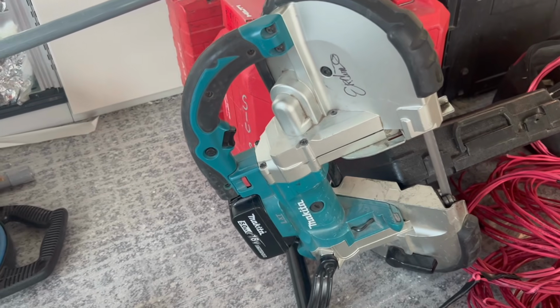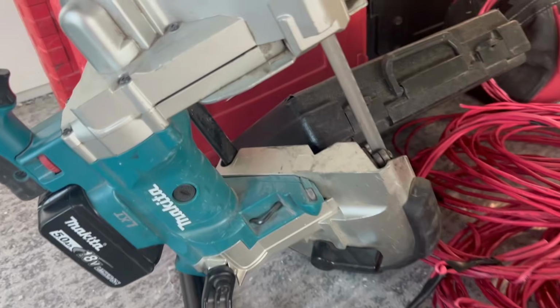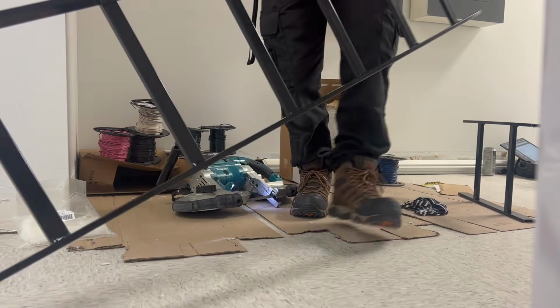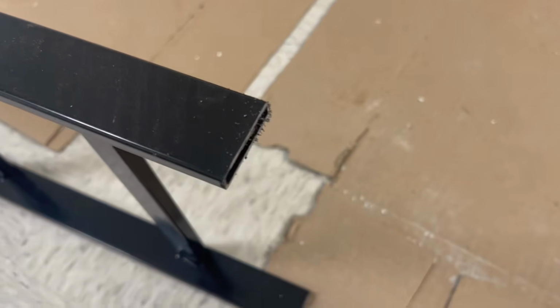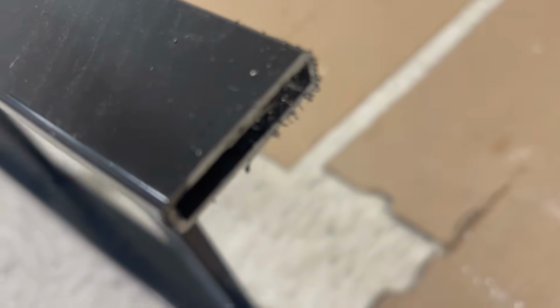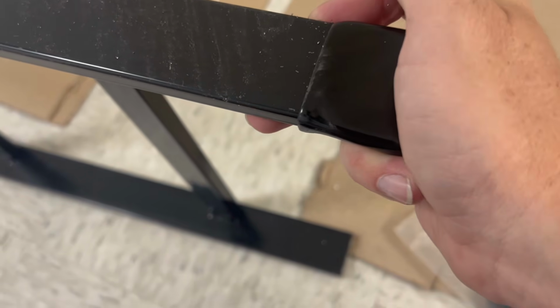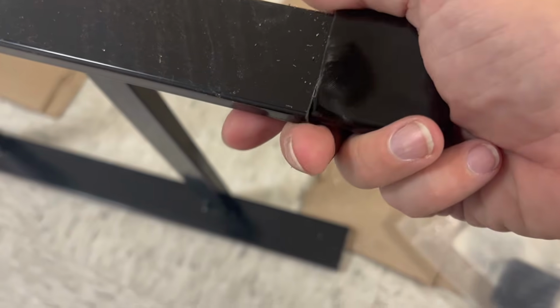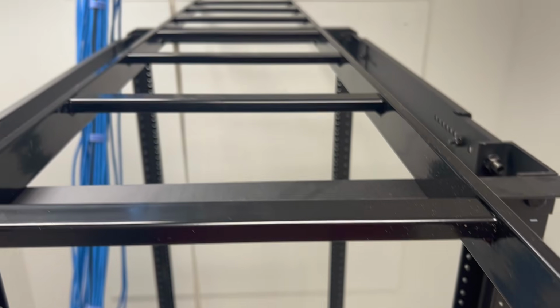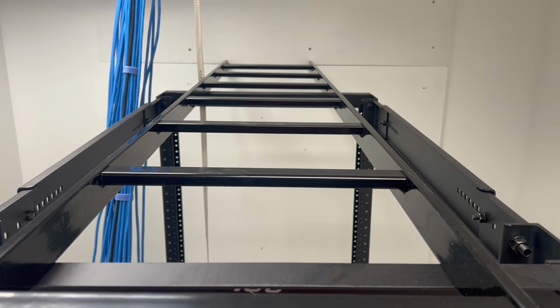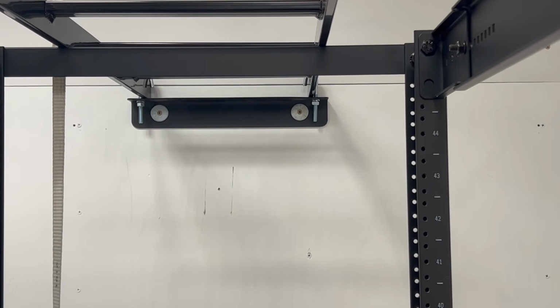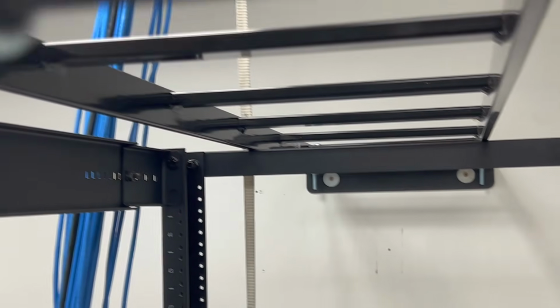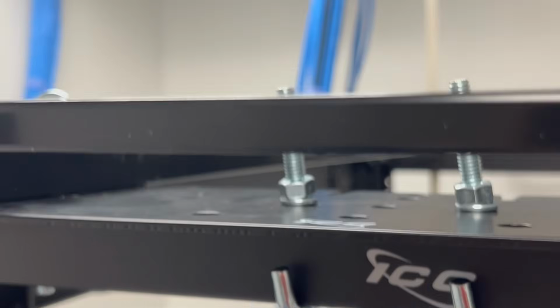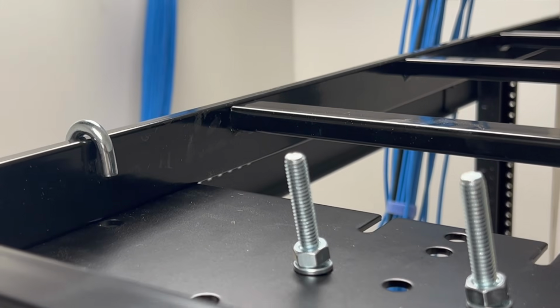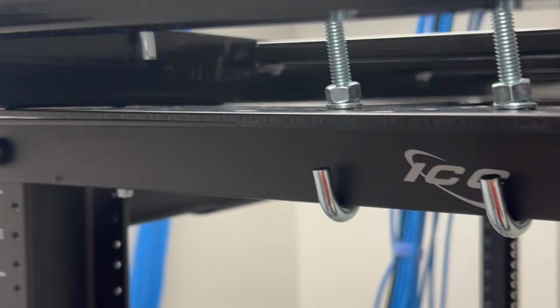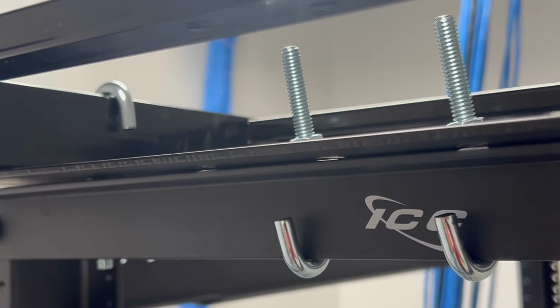To cut it down, I'll use a bandsaw to quickly cut through each side. Once the cuts are made in the ladder, I'll cover them with silicone so the edges aren't sharp, then lay it back on top of the server rack. I'll use the included J-bolts to lock it sturdily to the plywood, then use a top plate adapter that ICC provides for this rack model to firmly lock the ladder tray to the top of my server rack.